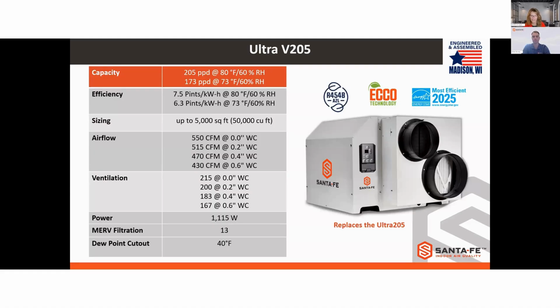And again, we can get a lot of ventilation. At 0.4 inches of static, we can still get 183 CFM of ventilation going through this dehumidifier. And it has the MERV 13 filter. And again, we have that 40 degree dew point cutout incorporated into this unit as well.